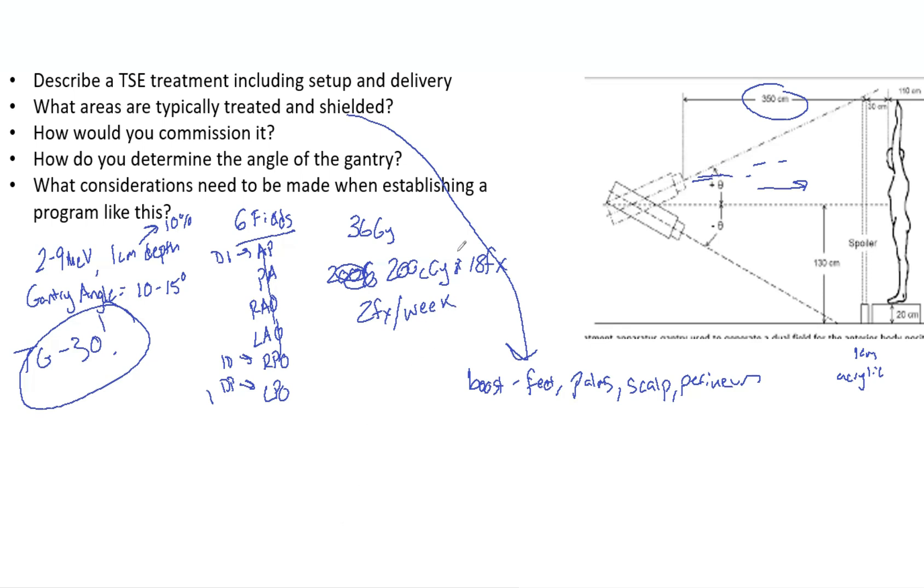commissioning: how would you determine the angle of the gantry? Say you don't have a TSE program but they want you to have one. First, you need TLDs for in vivo dosimetry, you need RANDO phantoms to test, and you need your exact treatment parameters—how much room is there between the gantry and the patient.